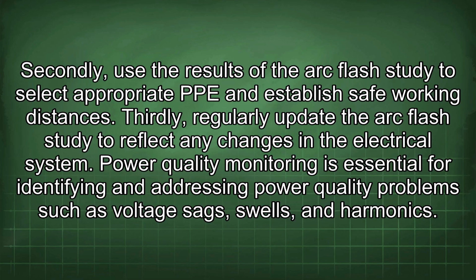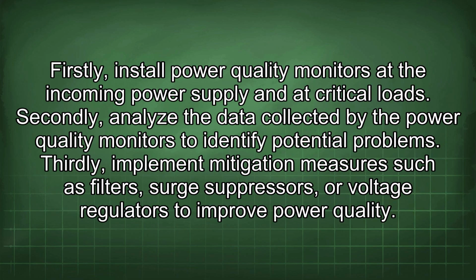Power quality monitoring is essential for identifying and addressing power quality problems such as voltage sags, swells, and harmonics. Firstly, install power quality monitors at the incoming power supply and at critical loads. Secondly, analyze the data collected by the power quality monitors to identify potential problems. Thirdly, implement mitigation measures such as filters, surge suppressors, or voltage regulators to improve power quality.